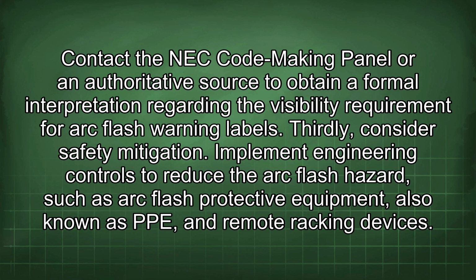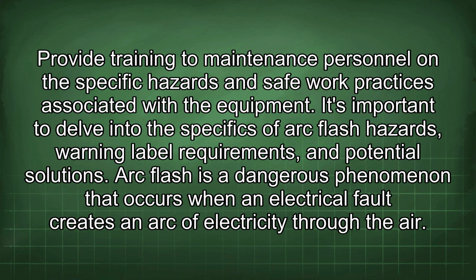Thirdly, consider safety mitigation. Implement engineering controls to reduce the arc flash hazard, such as arc flash protective equipment, also known as PPE, and remote racking devices. Provide training to maintenance personnel on the specific hazards and safe work practices associated with the equipment. It's important to delve into the specifics of arc flash hazards, warning label requirements, and potential solutions.